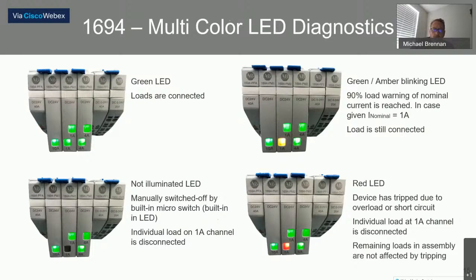So you can manually switch the circuit on and off by pushing that LED. So that's very nice for troubleshooting. Now again, that doesn't preclude lockout tagout. So we shouldn't use that in an application to go in and do individual diagnostics or checking. We want to make sure that we follow all safety rules, but it does allow you to easily switch off. If you're in the testing phase, you can individually switch off a circuit.